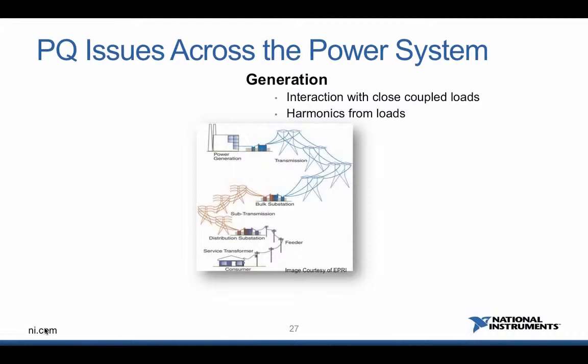So for instance, the generation. The generation issues connected with power quality might be the interaction with the close coupled loads, for instance, or the harmonics coming from the loads. Basically, many of the appliances, many of the loads which are currently connected to the grid are non-linear loads. It's not just simple resistors, like it was a couple of decades ago, but today almost everything is powered by thyristor converters or some switching units which drive or control the amount of power which goes from the grid to our appliance. And when we switch something, it typically generates a lot of higher harmonics.